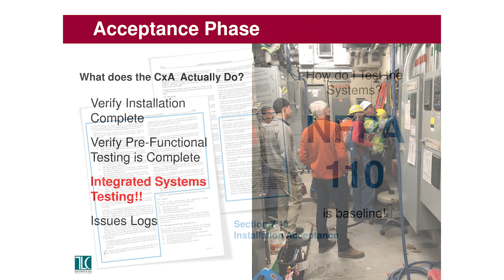This is the fun stuff. This is what we want to talk about, right? So what do we do? We test stuff, the same thing we do on the HVAC side. People ask me, how do you go about testing the systems? And I tell them that we start with NFPA 110. That is kind of the Bible for what we need to do for installation acceptance testing. That's how we base most of our tests, making sure that we are complying with all of the requirements of NFPA 110 and basically writing the test procedures around making sure that those requirements are met, of course with the OPR and the BOD as well.